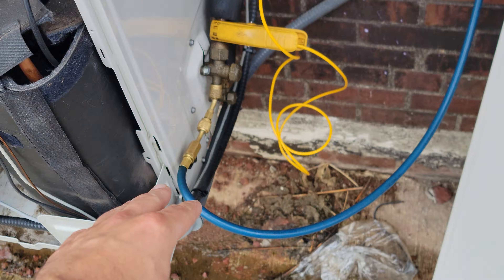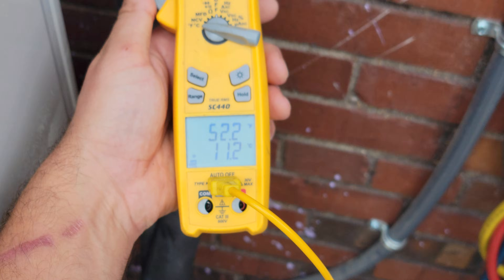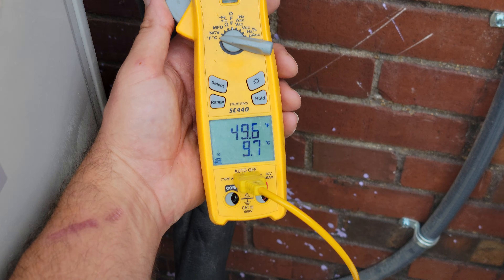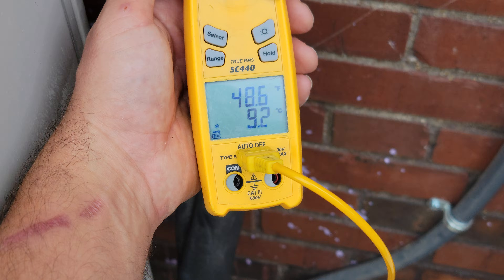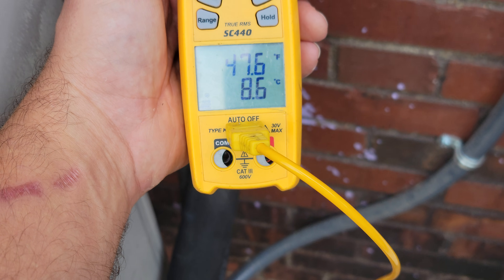Checking the temperature of the vapor line, the suction line here, with my Fieldpiece SC440. We've got 50 degrees, 49, 48 degrees — 47 degrees. That's pretty good.